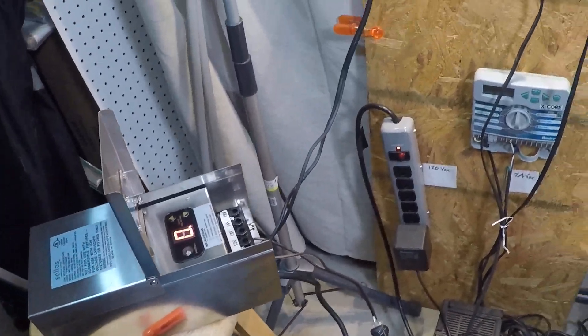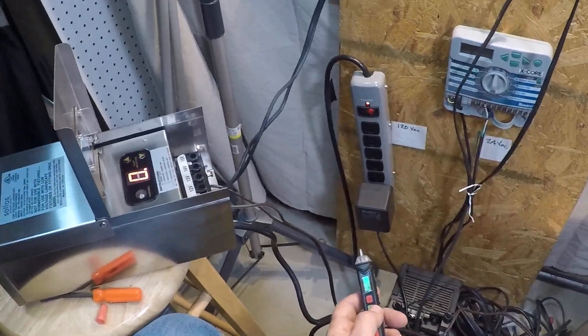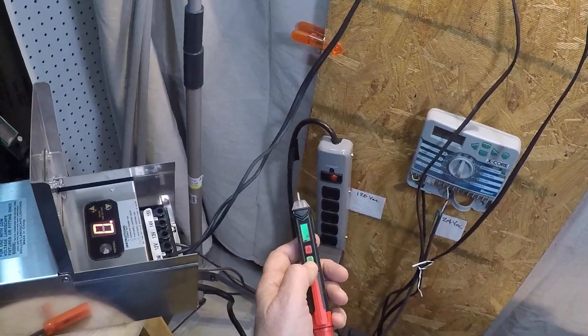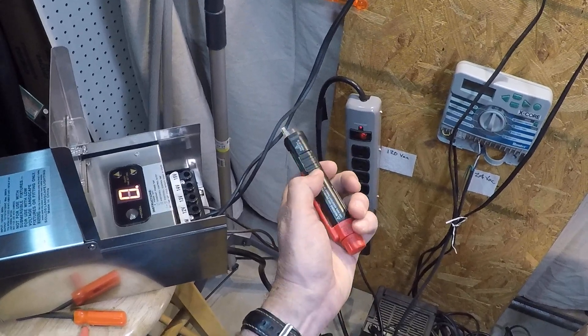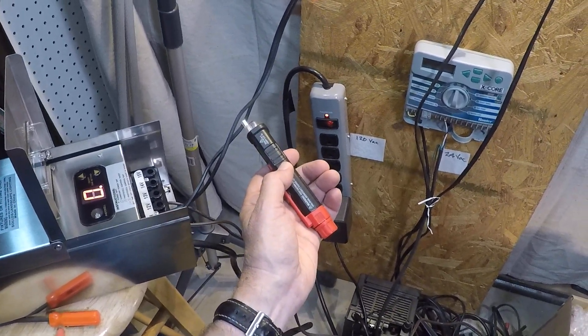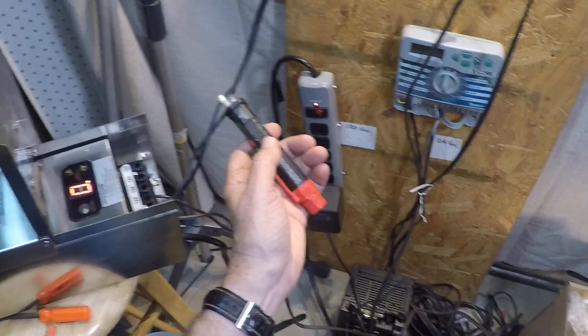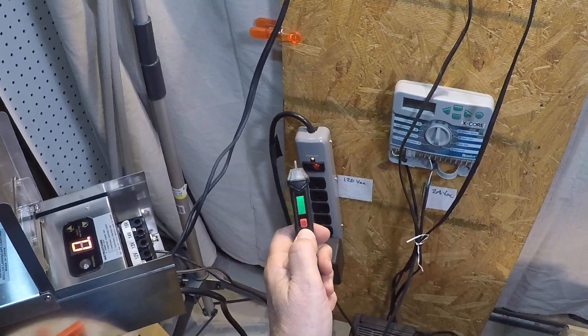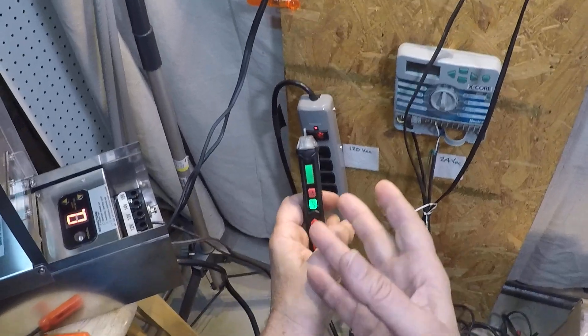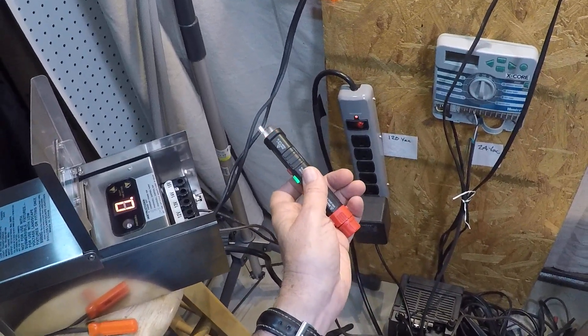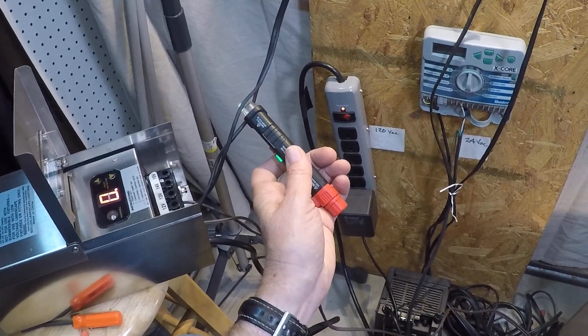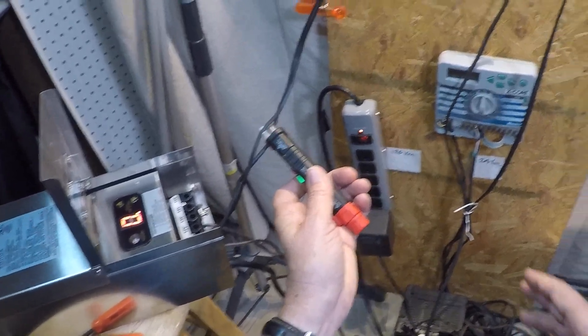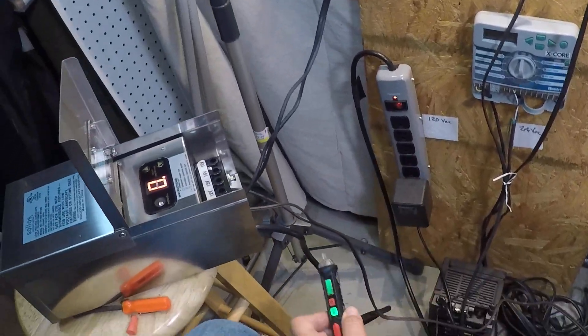Right now the transformer is on, so it's providing lighting power up here. Typically you see I cannot detect the 12 or 24 volt signal here. This is 12 volt lighting. I'm not detecting it with the pen. I push this button, the second green button. The light comes on. I'm now in the higher sensitivity mode, and it detects that I have 12 volts AC on this wire going up to the lighting system.